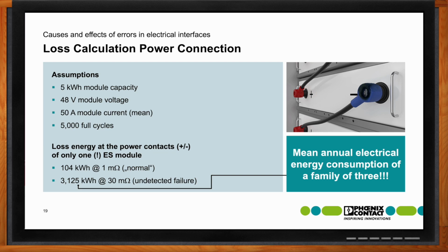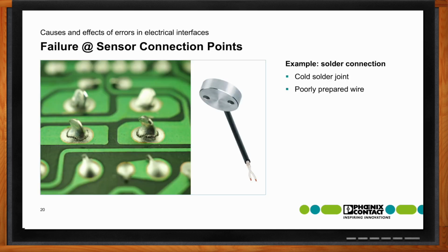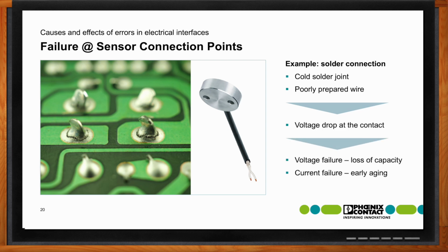So, Rudy, can there also be a failure at the sensor connection level as well? Absolutely, yes. If you look at this picture, you see a sensor which in many cases is directly soldered into the PCB, the wire ends. In this case, we can have, for example, cold solder joints or poorly prepared wires, which would result in voltage drop at these contacts. That means the sensor is measuring the wrong signal, which would end up, for example, in case of voltage failures, in loss of capacity of the battery, or in case of current failures, in early aging of the battery because we would charge and discharge with too high or too low a current.